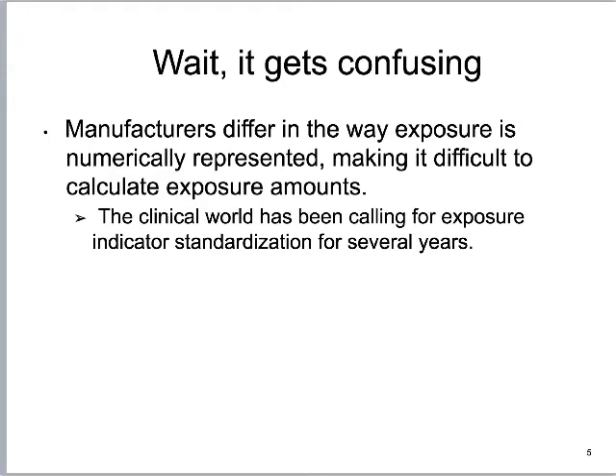Unfortunately it gets confusing. They gave us this exposure indicator — thank you, nerds who write computer programs — but every single manufacturer out there, Siemens, Kodak, GE, Fuji, all used different exposure indicators based on completely different math. This made a complete muddle for technologists. If you're working on a Fuji machine and shoot an exam, that exposure indicator number is completely different from a Siemens machine — one goes smaller as you overpenetrate, the other gets larger. They're completely different scales.